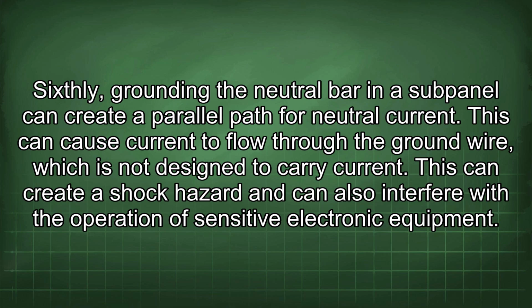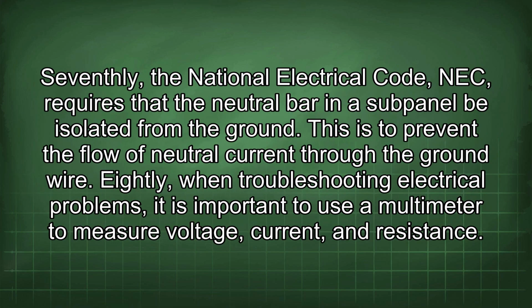This can cause current to flow through the ground wire, which is not designed to carry current. This can create a shock hazard and can also interfere with the operation of sensitive electronic equipment. Seventhly, the National Electrical Code (NEC) requires that the neutral bar in a subpanel be isolated from the ground. This is to prevent the flow of neutral current through the ground wire.